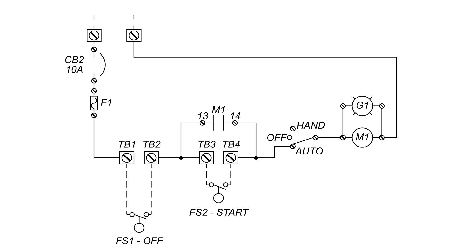Here in this schematic we have a circuit breaker, fuse, two float switches, the latching contacts labeled M1 on the left, the HOA switch in the auto position, the green pump run indicator, and the motor labeled M1 on the right. When power is connected to the panel, it will not pass through the circuit breaker. When the circuit breaker is turned on, the power will pass through and end at float switch one — the off float. The panel will remain this way until the water rises.